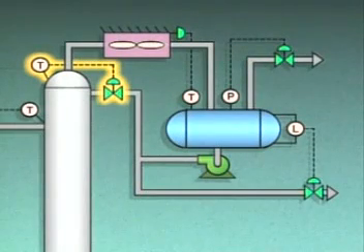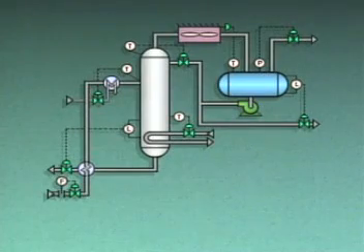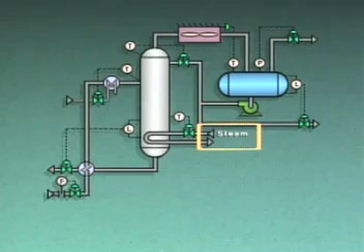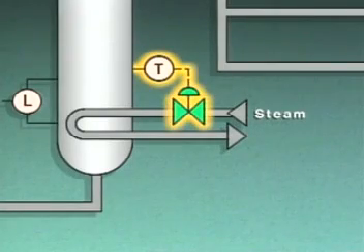When the external reflux control loop senses a decrease in the temperature, it decreases the flow of reflux to the tower. In some distillation systems, the external reflux flow is kept constant. The amount of condensation is varied by changing the temperature of the reflux. Introducing cooler reflux into the tower has the same effect on product composition as increasing the flow of reflux to the tower. In this system, the bottom temperature is controlled by adjusting steam flow to a stab-in reboiler. This is accomplished by the bottom temperature control loop.